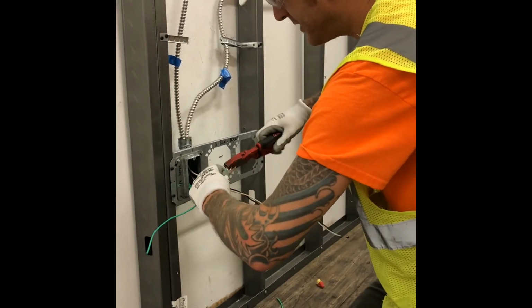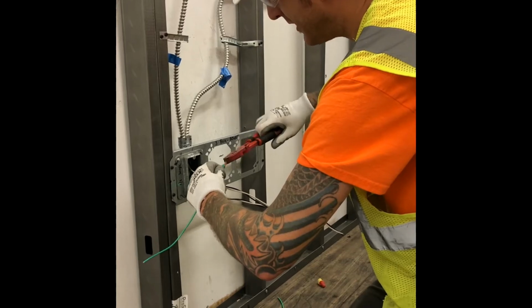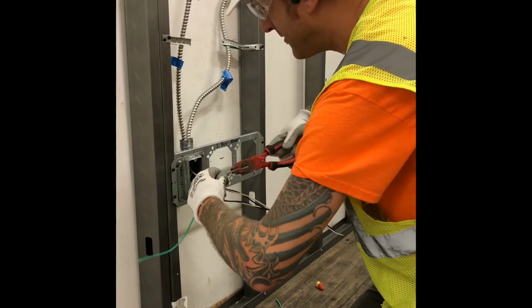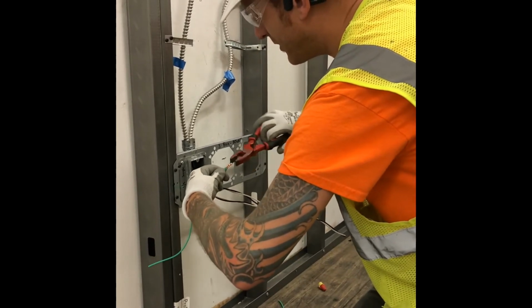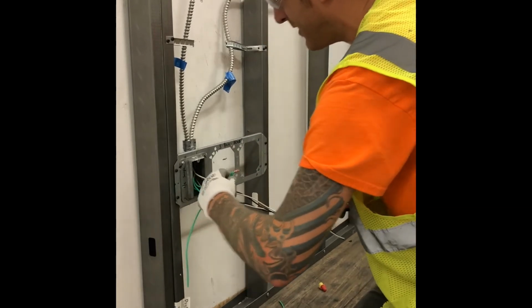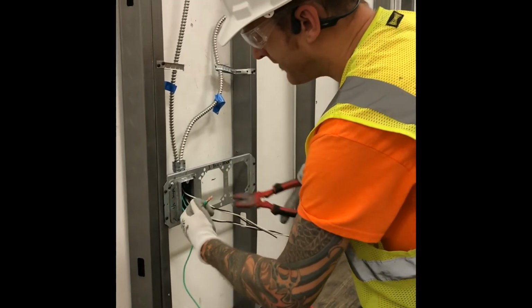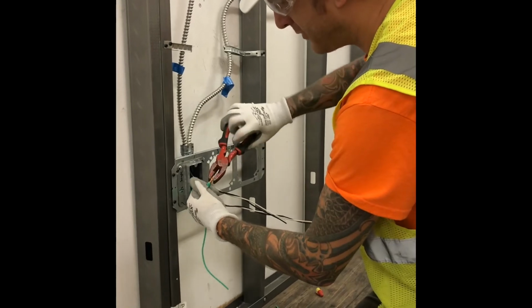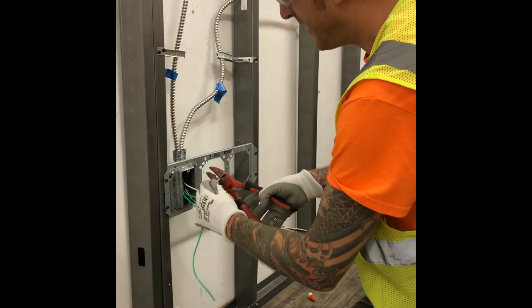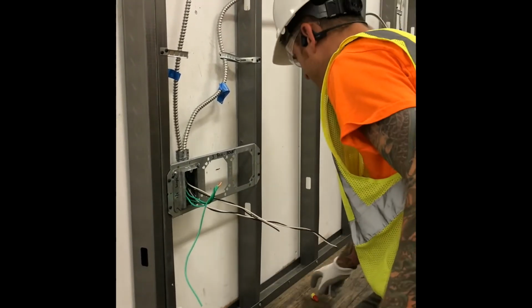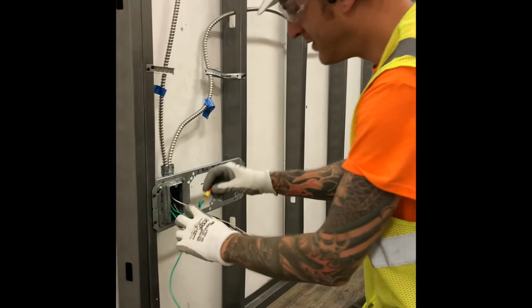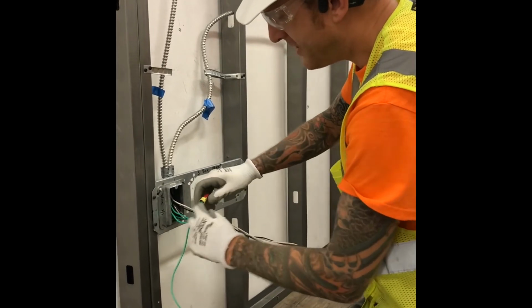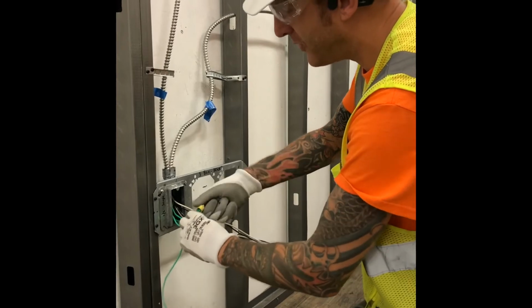This will take practice, but you just kind of loosely get them together, and as they start forming into each other, that's when you can start getting tighter. See how it creates a little groove there? Then I like to snip a little bit off, and it's ready for the wire nut. Put the wire nut on, making sure the exposed copper isn't beyond where the wire nut is.